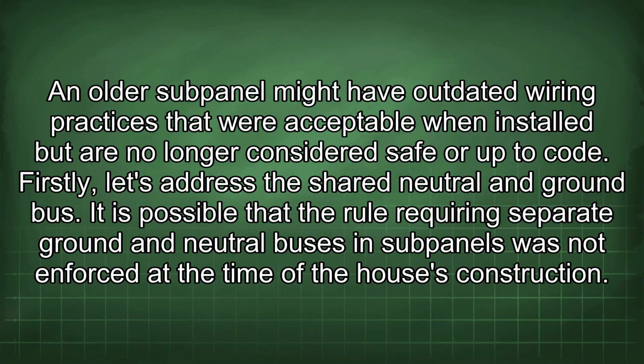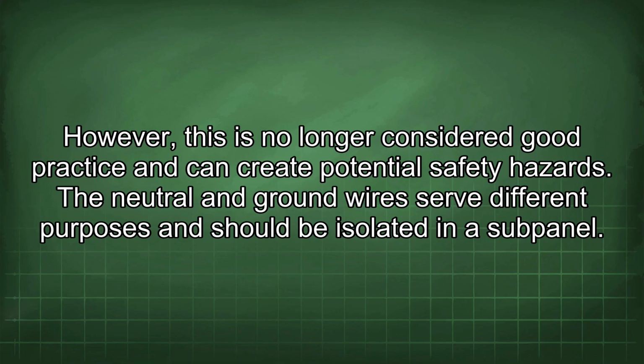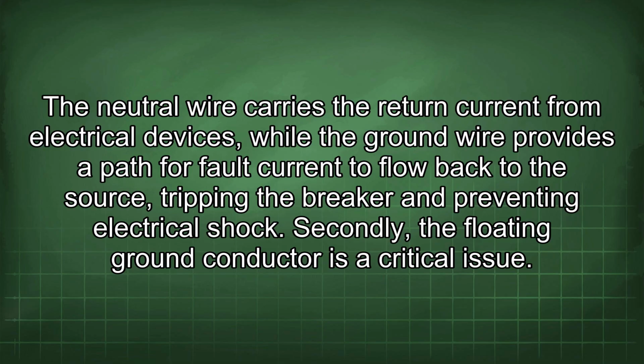An older subpanel might have outdated wiring practices that were acceptable when installed, but are no longer considered safe or up to code. Firstly, let's address the shared neutral and ground bus. It is possible that the rule requiring separate ground and neutral buses in subpanels was not enforced at the time of the house's construction. However, this is no longer considered good practice and can create potential safety hazards. The neutral and ground wires serve different purposes and should be isolated in a subpanel. The neutral wire carries the return current from electrical devices, while the ground wire provides a path for fault current to flow back to the source, tripping the breaker and preventing electrical shock.